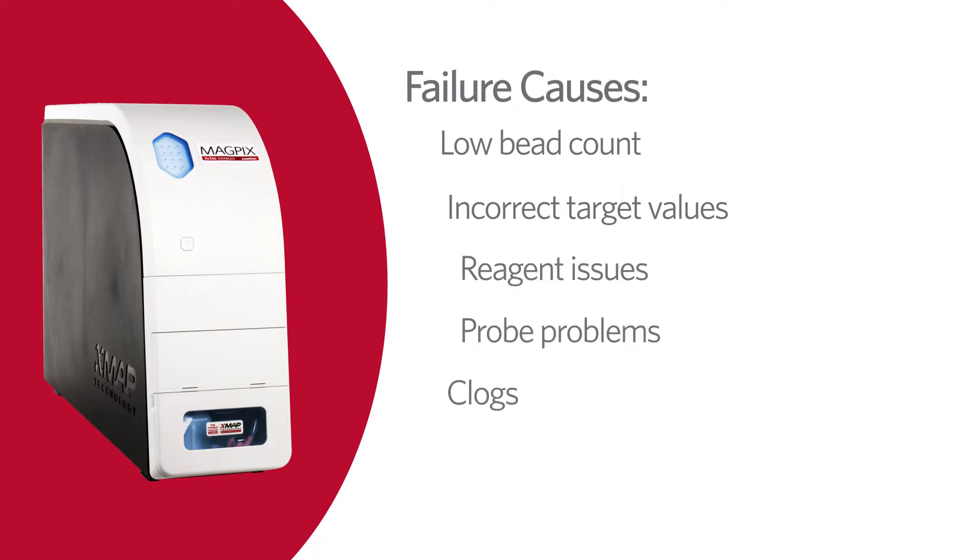Often, MAGPIX calibration and performance verification failures occur because of low bead count, incorrect target values, reagent issues, probe problems, clogs, or debris in the imaging chamber.